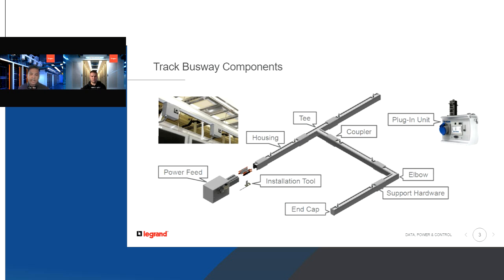You're seeing straights, elbows, and T's, which you use to customize the system to virtually any application, including data centers. But typically in data centers, we're not seeing a lot of T's or elbows - they're essentially all straight runs, whether it's a 20, 30, or 40-foot straight run, going from the power feed out to 20 or 30 feet of busway. Then to draw power from the busway to the load, you're using a plug-in unit pictured on the right, which draws power from the bus to whatever you're powering down underneath - in this case, for a data center, a server rack.